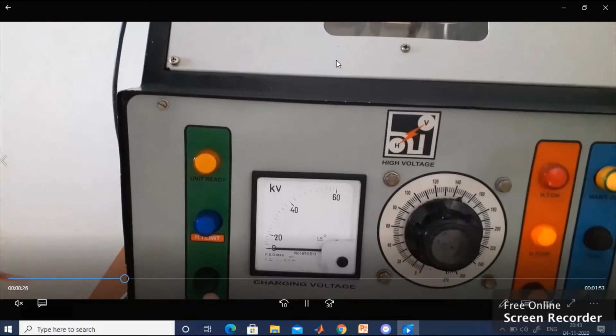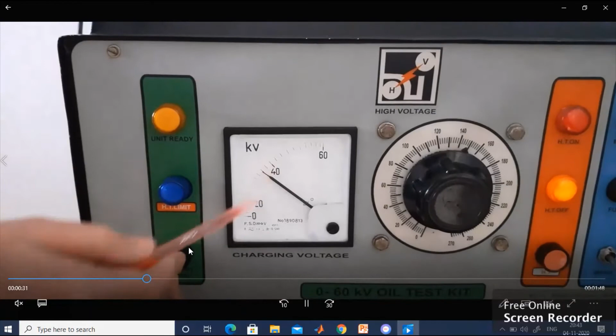See, whenever a spark or any other observation is made, that means dielectric breakdown has taken place. So you can measure the voltage by pressing the memory button. It will be approximately 36 kV, so the breakdown strength of that particular transformer oil is 36 kV. You can measure and note it down in the table.